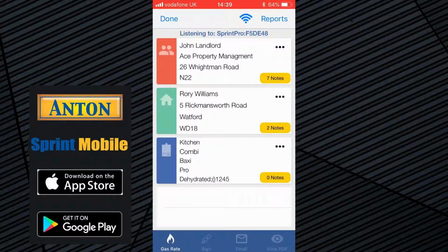I've already created some reports here, some flue gas reports for this customer. Obviously, you would normally need to do that. You take your flue integrity test. I'm talking about a high efficiency boiler here, so a low fire and a high fire. But you can also add let by and tightness test if you've done one with your analyzer, so you can incorporate that. Operating or working pressure, gas rate. So let's get into the detail of it.